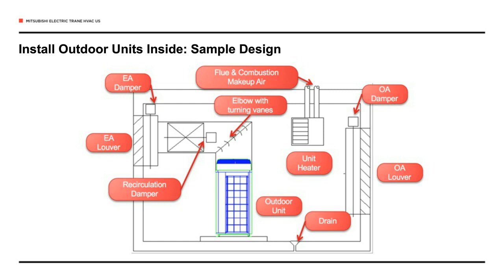And by using the unit heater, typically gas or maybe hot water, as we use that unit heater to heat that room, that heat then gets absorbed through the condenser coil and gets transmitted into the building by the VRF system. So you get the additive nature of the unit heater heat and the VRF heat added to it to heat the building. So it's one nice central location to put your auxiliary heating equipment.